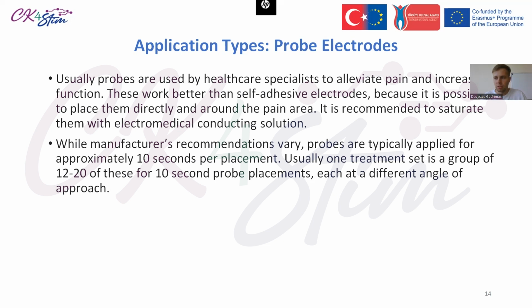So it is quite an advantage to have a probe versus self-adhesive electrodes, because the probe can be placed in various places, and these places can be changed quite fast. And usually manufacturers' recommendations vary. Probes are typically applied for approximately 10 seconds per placement. So we use 10 seconds on one point of pain, for example, then we change, and this way we can go, for example, around the knee joint quite well, because we reach many spots around the knee joint.